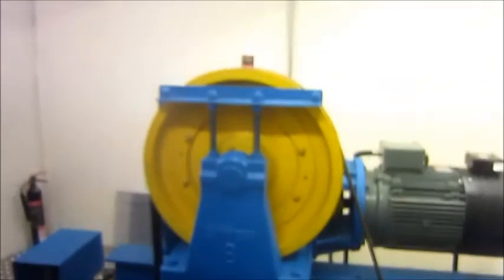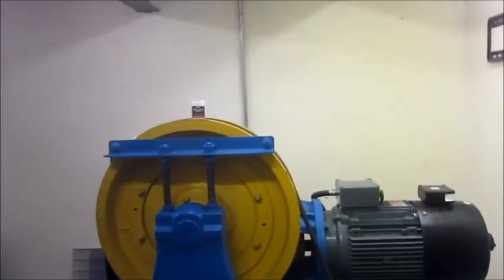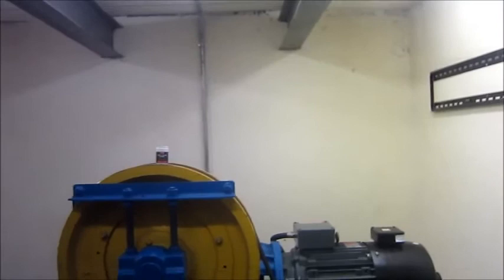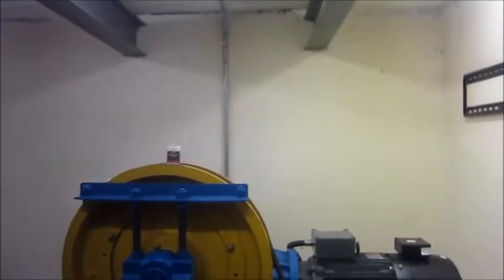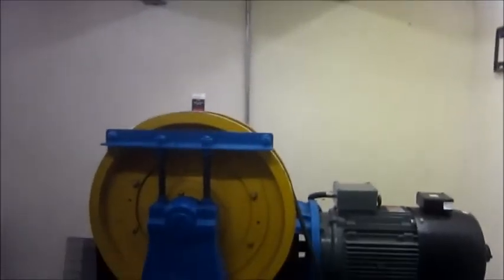But also on the bottom, you have to have enough room for it to shoot past the bottom floor. And there are hydraulic buffers, so that if the car, not dropping at a million miles an hour, travelling at a normal speed, for some reason hasn't stopped at the ground floor, there's a buffer that will hit, like you get on the front of trains. That is tuned to the right mass and speed of the lift, so that the people inside stop at a humanly acceptable rate, and they're not just squashed. The pit.